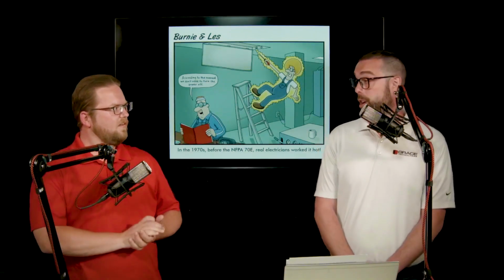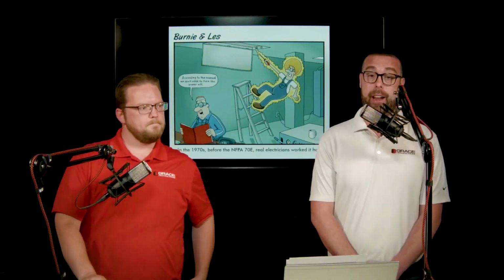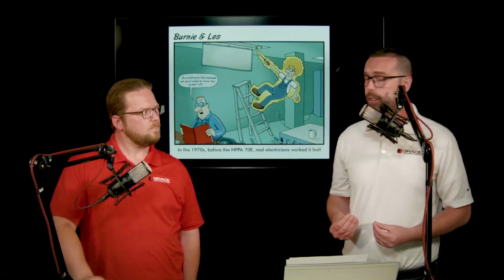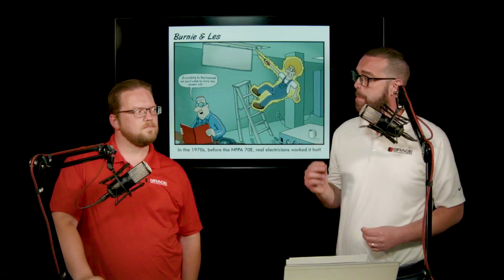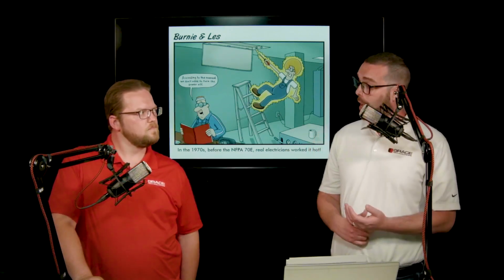Yeah, you ask a great question, and I'm glad that we'll be able to get that answered here. So the whole idea is with our permanent electrical safety devices, we're not necessarily changing the lockout tagout procedure like you mentioned. We're in essence adding these externally mounted devices and wiring them in parallel to the source voltage. So again, it's acting as an extension of that source voltage, right? So with the implementation of the check volt, for example, this is a great solution that has built-in dual redundant LEDs along with contact high impedance test points.